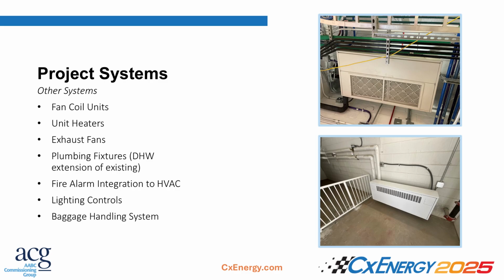Some other systems in the airport included fan coil units. There were several electrical rooms and telecom rooms with a lot of crucial equipment for CLT operations, so they had these fan coil units to cool the spaces. There were also unit heaters, exhaust fans, and both tank and tankless water heaters that we tested. We also tested the fire alarm integration into the HVAC system, making sure all the air handlers shut down if the fire alarm went off.